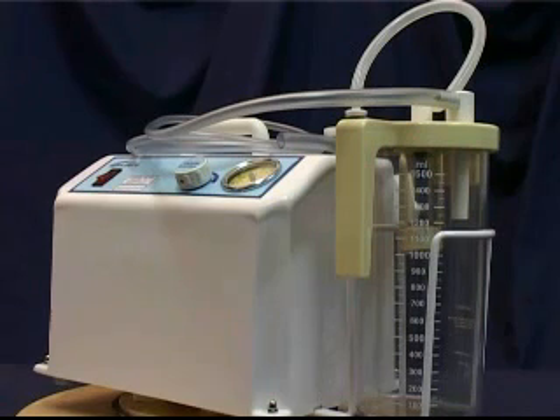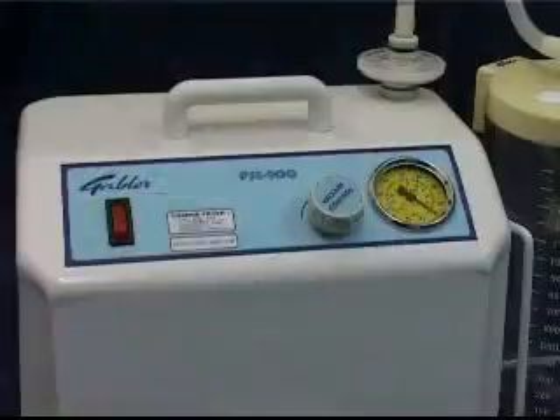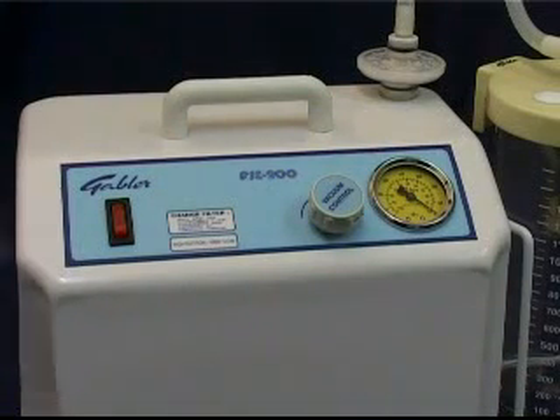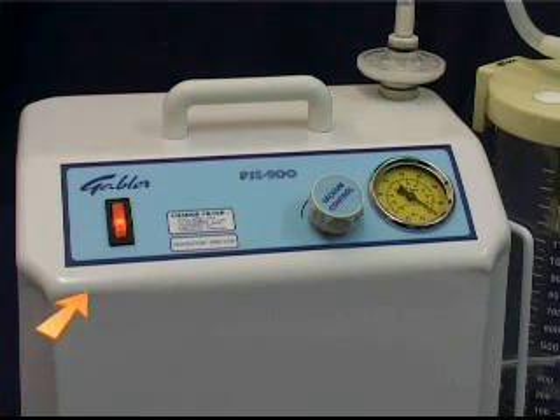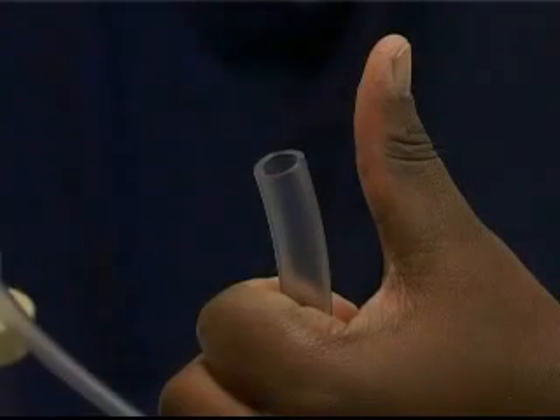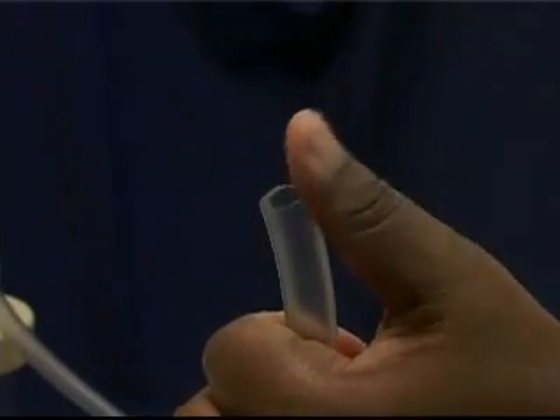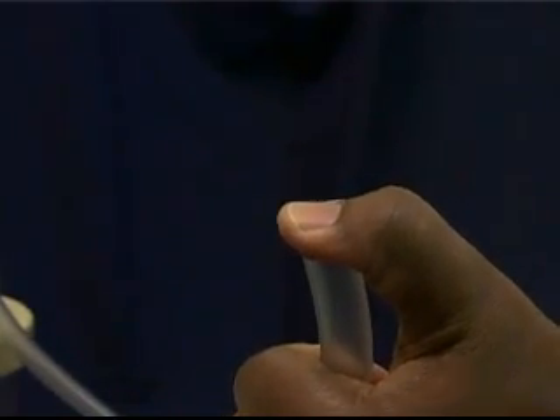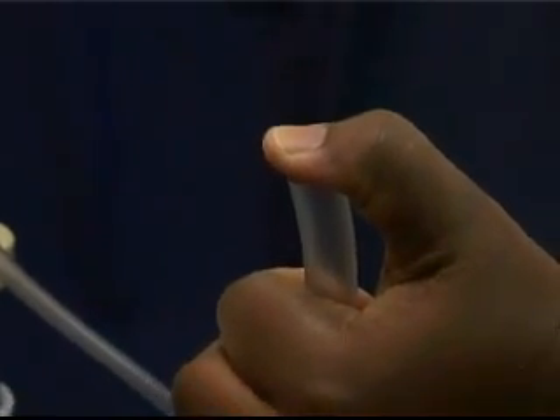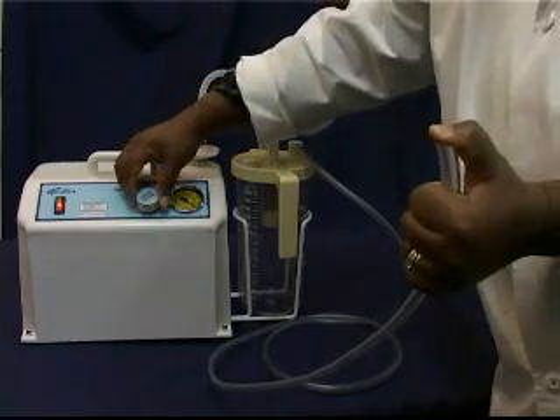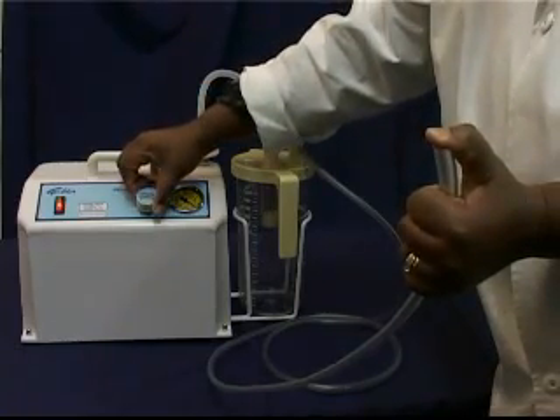With the daily inspections completed, we can now start using the equipment. First, switch the unit on by means of the on-off switch. The red neon lamp in the switch will illuminate, indicating that the unit is on and ready for use. Now block the tube fitted to the patient inlet of the collection jar to check the vacuum. Adjust the setting with the pressure control knob if necessary.